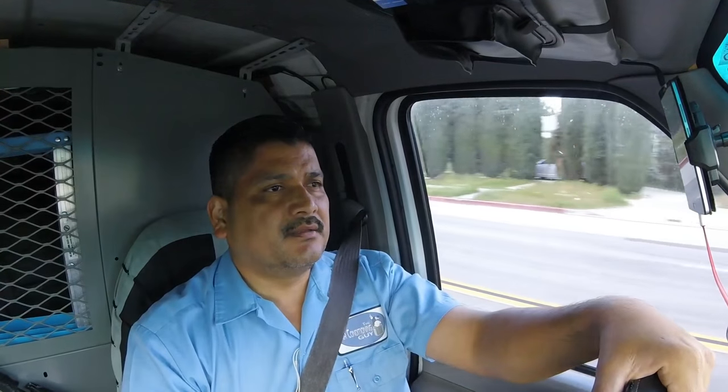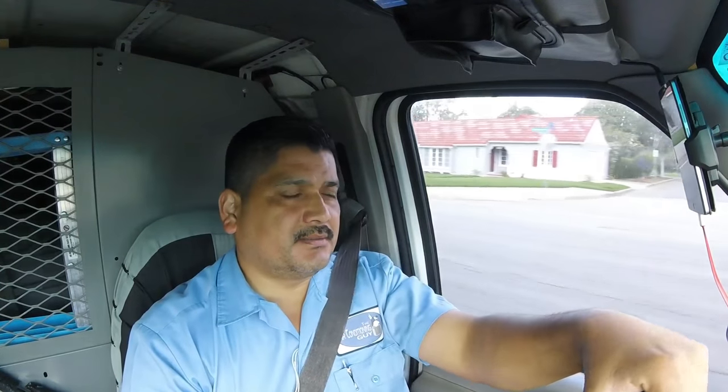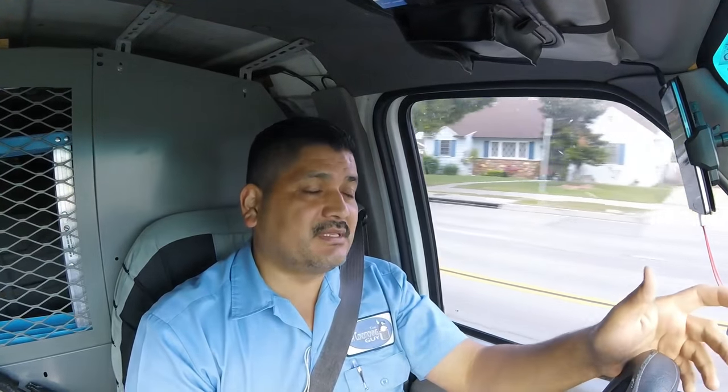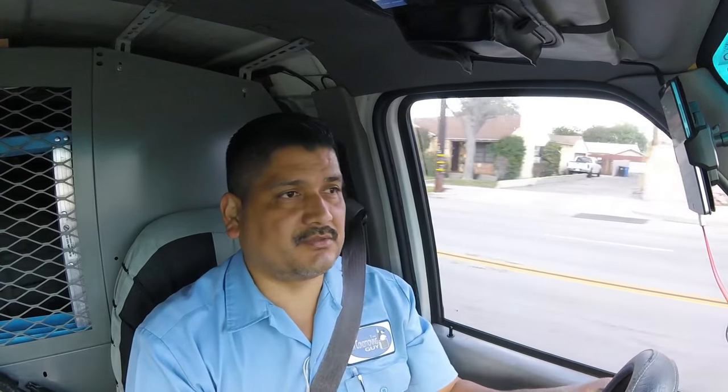The problem that they're having is that their AC doesn't work because somebody pulled out the compressor. Maybe they were gonna fix it and they never fixed it. For whatever reason, they don't have the compressor. I know it's not theft because if they would have stolen anything, they would have stolen the coil, not the compressor. Compressor is worthless for scrapping. So we have to replace the AC and we have to use that existing furnace.